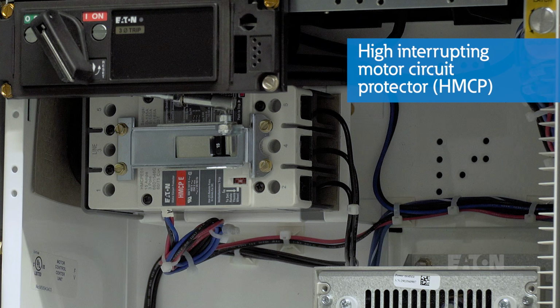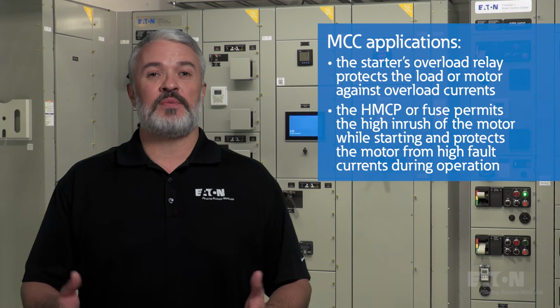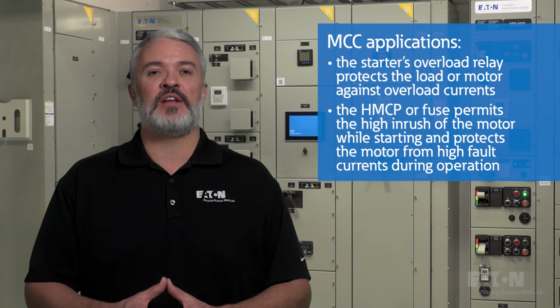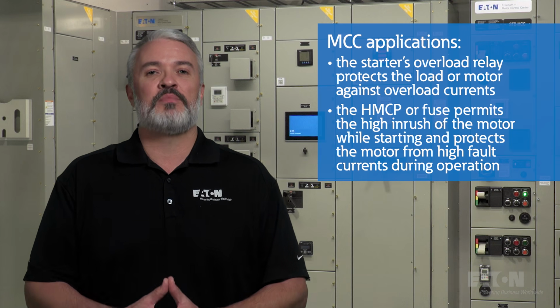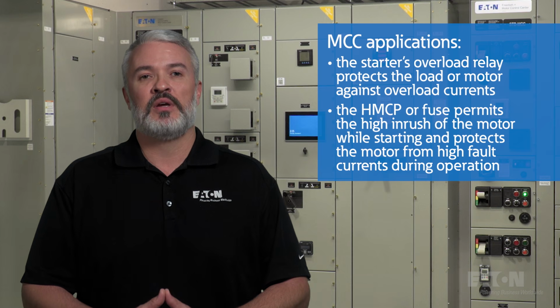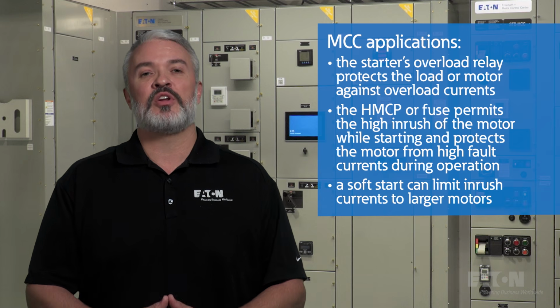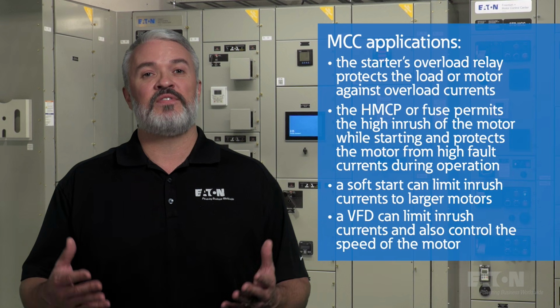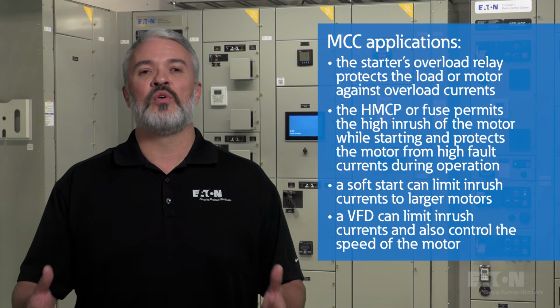A typical bucket used for motor protection and control consists of a starter and a disconnect device of proven capability. The disconnect device can be a high interrupting motor circuit protector or HMCP, thermomagnetic breaker, or fusible switch. In a motor control center application, the starter's overload relay protects the load or motor against overload currents. The HMCP or fuse are used to permit the high inrush current of the motor while starting and protect the motor from high fault currents during operation. A soft start can be used to limit inrush currents to larger motors. A VFD can also limit inrush current and control the speed of the motor.